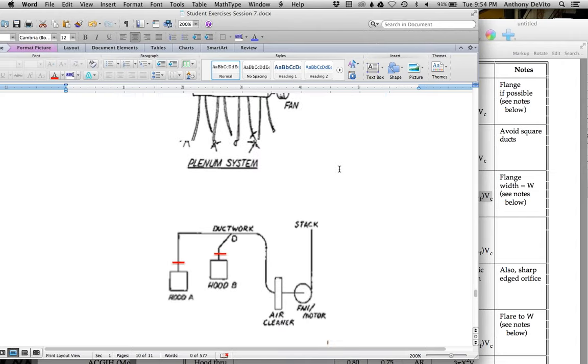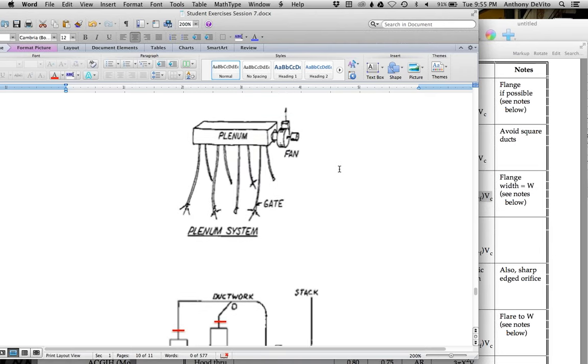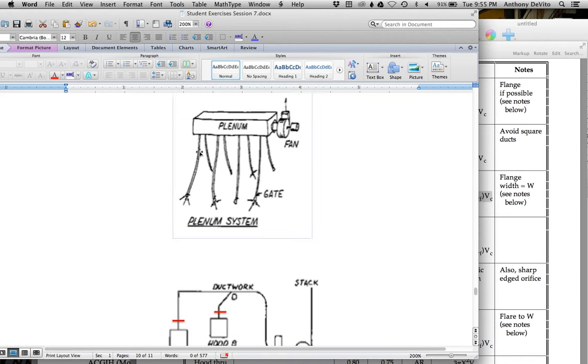Just one other thing, just want to talk about quickly, because it's on the PowerPoint. You can actually go through the PowerPoint on your own, and the one that we have from Jeff. Three types of systems. One type is a plenum type. You guys have gone into garages and you've seen, when they work on your car in a garage, these big service centers, they have like a 4 or 6 inch flex duct that comes down from the ceiling, and they connect it to your exhaust pipe so they can work indoors, right? That's a hood. And the way that works is they use a big plenum. They use a big duct with a fan that keeps that duct under the same pressure, because all of those hoses are the same size.